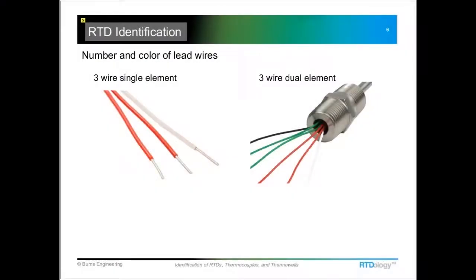The first thing to notice is what kind of lead wires are in it, count how many there are and what the colors are. So for a single element RTD, we have just typically two red leads and one white, and if it's a dual element there's going to be six wires, still going to have the two reds and a white being one sensing element, and green and black would be the other.